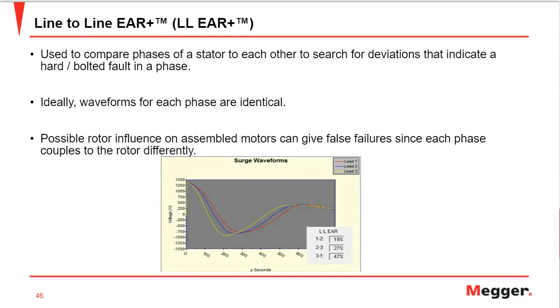Line-to-line works well with a motor without the rotor installed, because the coils are nearly identical, and testing assembled motors, or with the rotor installed, is not straightforward. It's not straightforward because, depending on where the rotor slots are with respect to the stator coils, there would be different coupling ratios for all three phases. So it is usually recommended during field testing that we do not compare the waveforms, and use pulse to pulse EAR. For motor shop testing, where we have to compare the waveforms, of course, when there is no rotor influence, we can use line to line EAR.